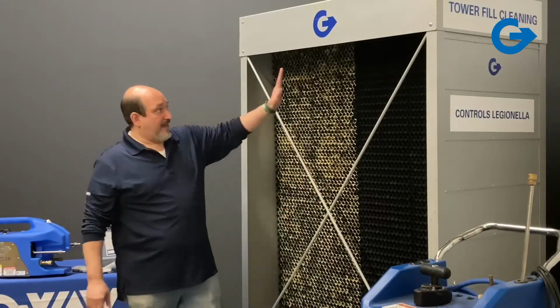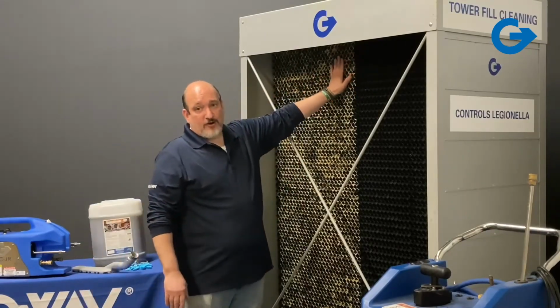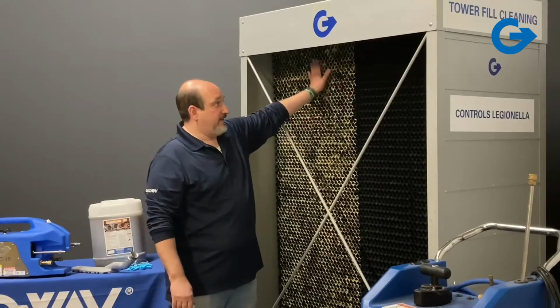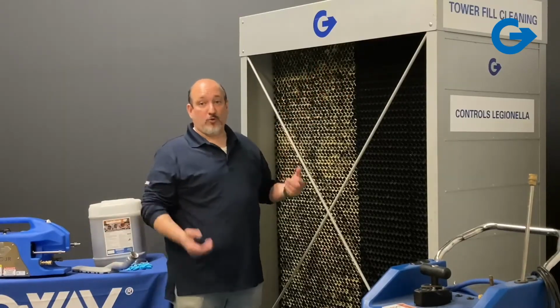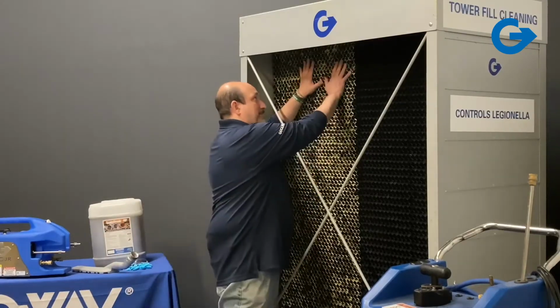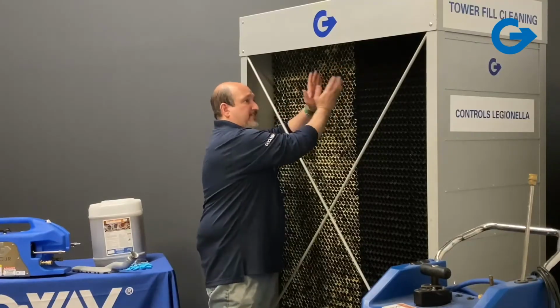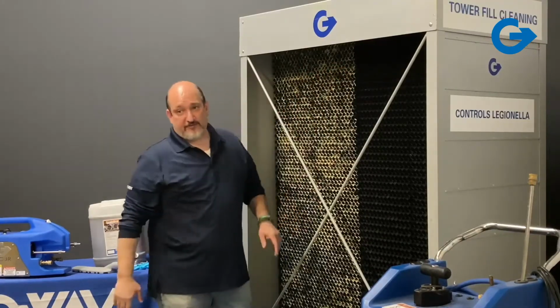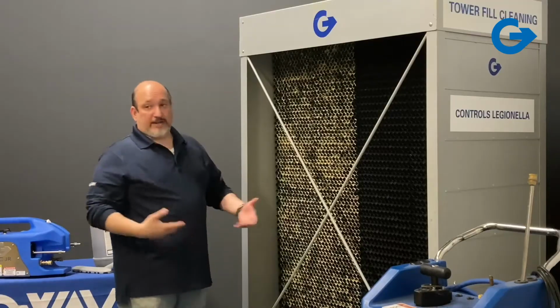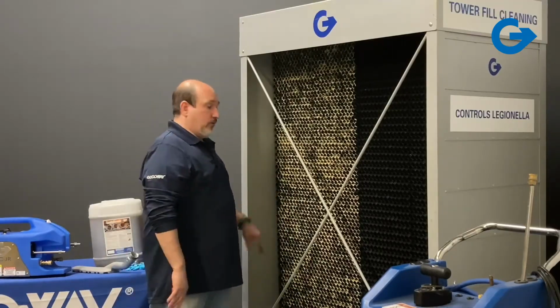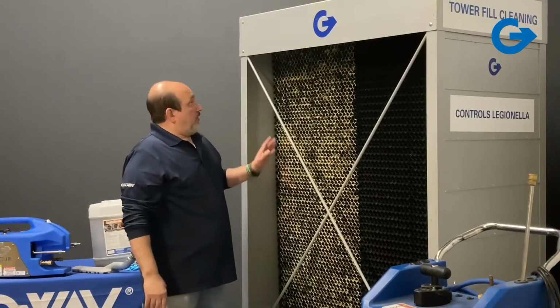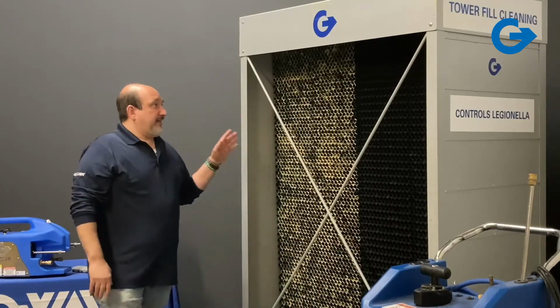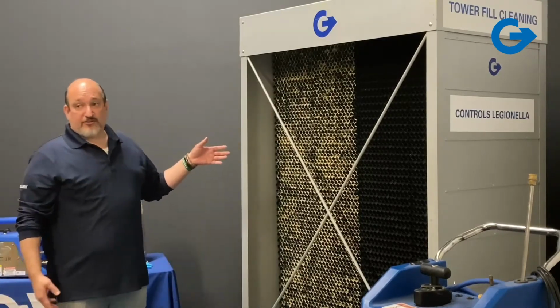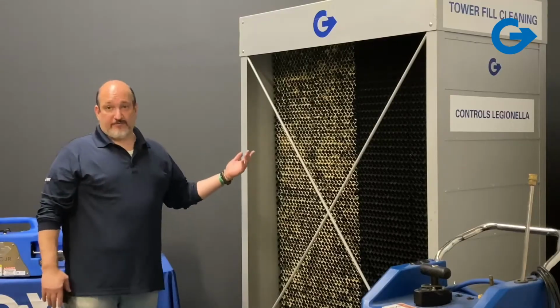So you really want to have that uniform pattern of a thin sheet of water coming down the entire surface of your fill to get the proper cooling. And when you have big patches of scale, the water tends to channel and not cool nearly as efficiently. And your system is working harder to try and get the same kind of cooling done. So we wanted to have something that allowed you to clean scale as well as biological growth without damaging the fill.